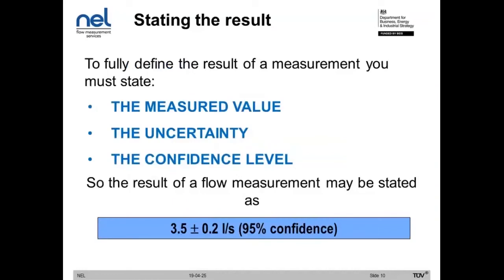When you have a measurement, it's important to express three different aspects of the measurement. First of all, we have the measured value, but we also have to express the uncertainty interval and the confidence we have in the uncertainty interval. In this case, our example is a flow measurement. We've measured 3.5 litres per second, and the uncertainty interval is plus or minus 0.2 litres per second. And the confidence level that we have for this uncertainty level is 95% confidence. So what we're saying is that 95% of the time, we expect the true value of the measured parameter to lie within this uncertainty window. So we expect the true value of the parameter to lie between 3.3 and 3.7 litres per second. We'll talk about where this number of 95% comes from later on in the presentation, but this is a very common confidence level. In metrology, it's probably the most common confidence level that is used.